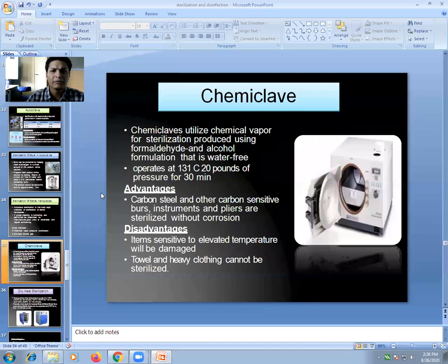Now coming to chemical vapor sterilization, here it operates at 131 degrees Celsius of temperature, 20 pounds of pressure, and time required is 30 minutes. So what chemicals are used? These chemicals are formaldehyde and alcohol formulations. These are water-free formulations.